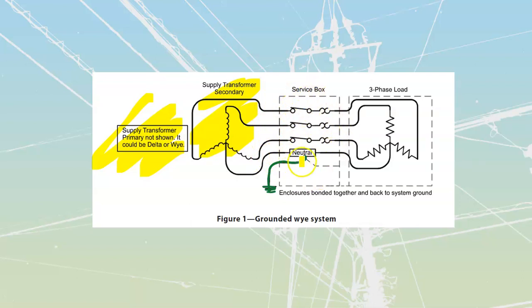In this case, we've got a fusible disconnect over here. From that service box, then we feed out to all the rest of our loads. And we see that we're also taking all of the boxes, and all of the boxes are going to get bonded together. So it's this dotted line that goes around the outside of all the boxes, as well as that dotted line is going to get connected back to our neutral at the main ground. This is going to be that bond screw or that ground screw that we're so familiar with. And there's a big reason for this that we're going to cover later on when we look at the current flow.